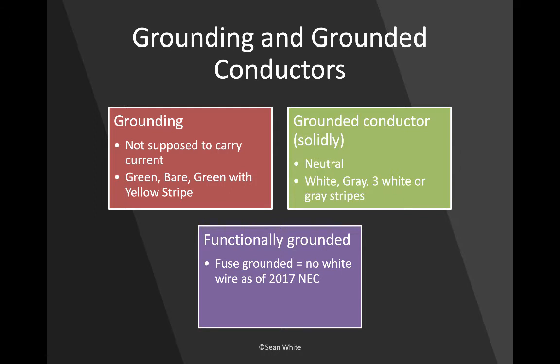So if you have a grounding conductor, like an equipment grounding conductor or a grounding electrode conductor, something where the word grounding ends with a G, then that wire should be green, bare, or sometimes green with a yellow stripe. Conductors are wires. For the grounding electrode conductor, we say GEC, that's connecting to a ground rod, and equipment grounding conductor, EGC. And so they're not supposed to carry current, and they can be green, bare, or green with a yellow stripe.